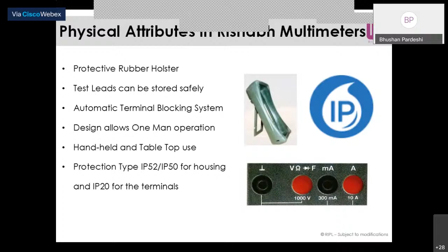So what happens in many cases in the field, while measuring different parameters, many times we forget that we have kept the probes at current measurement, and we have switched the knob to voltage, and we start measuring the voltage parameter. In that case, due to low resistance, current can pass through the multimeter, and the fuse mainly gets damaged, or many times the circuit might get burned out because of improper measurement of voltage in the current section. So that's why this facility is provided in the multimeter. While measuring current, I cannot switch the knob to voltage section unless I remove the current section. This is one of the features that we have provided in our multimeters for better protection of the user and for easy measurement.